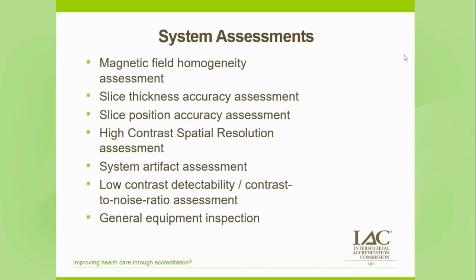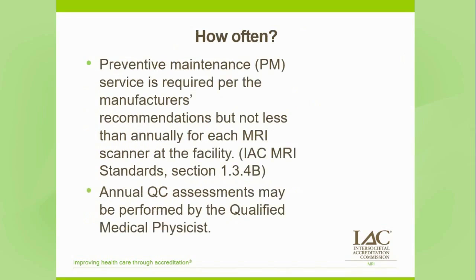Next, let's discuss how often the QC needs to be done. Since the focus of this webcast is periodic QC, the daily operator QC assessments must be performed each day that the magnet is in use. Beyond the daily assessments, the PM — preventative maintenance — performed by the service engineer must occur at the frequency specified by the manufacturer, but not less than once a year.